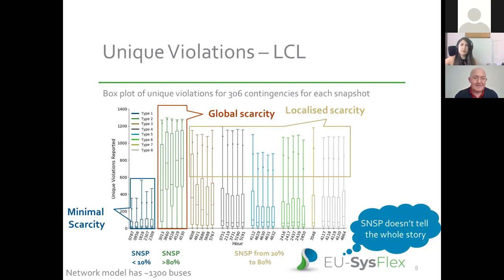However, we also see, as I've mentioned, that blue cloud, that those intermediate cases sometimes have problems and sometimes don't have problems. So renewable penetration doesn't tell the whole story. I think that's something you have to really think about when looking at these future cases. Just looking at raw renewable penetration won't tell you the full story. You have to understand what's left of the synchronous, where it is, and what fills up that. Say if you have 70% penetration, what makes up 30? If it's two large units, you're going to have very different behavior than dozens of small units. So that's something to bear in mind when you get presented with an SNSP number, what's really behind that.